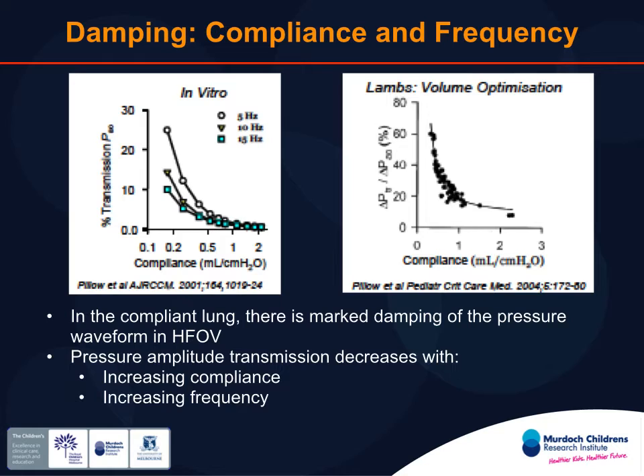It gets a bit more complicated than just the frequency itself and the ventilator you use. It's got to do with the lung mechanics as well. Different compliances within the lung will affect the effect frequency will have on tidal volume, because the compliance of the system will affect the transmission of pressure down the airway. So in a compliant lung, there's marked dampening of the pressure waveform. At different frequencies, you can see the percentage of delta P being delivered to the lung is actually relatively low.